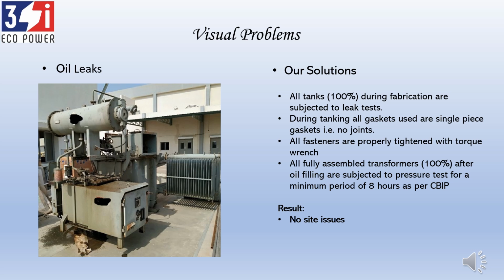From the pressure test, to the leak test at the fabrication stage, to using torque wrenches for gaskets, and finally the pressure test on a fully filled transformer - this ensures there are no leaks at site. We've supplied so many transformers so far and, touch wood, there are no field complaints at least on transformer leaks.